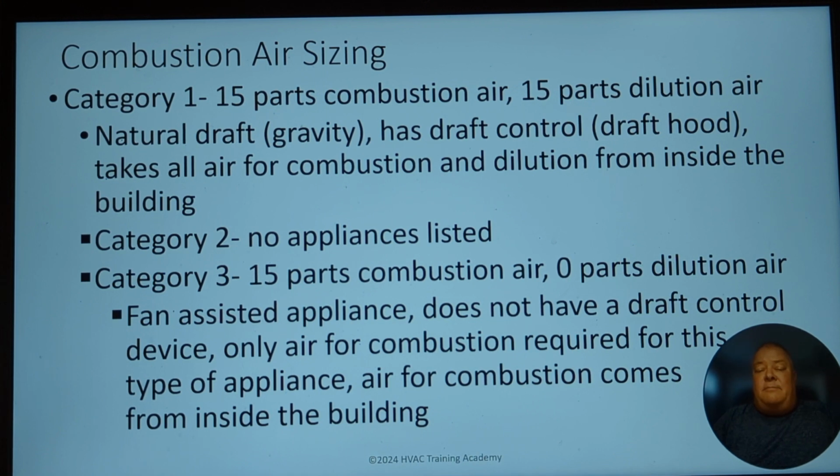So category 3, 15 parts of combustion air, doesn't require dilution air, so uses half as much air. It's a fan-assisted appliance, does not have a draft control device. Only the air required for combustion comes from inside the building itself. Now, you could have category 3, I have seen category 3 mid-efficiency furnaces that actually had a dedicated sidewall intake for air and also had an exhaust. So it's not automatically that all category 3 appliances are going to fit into this particular definition.